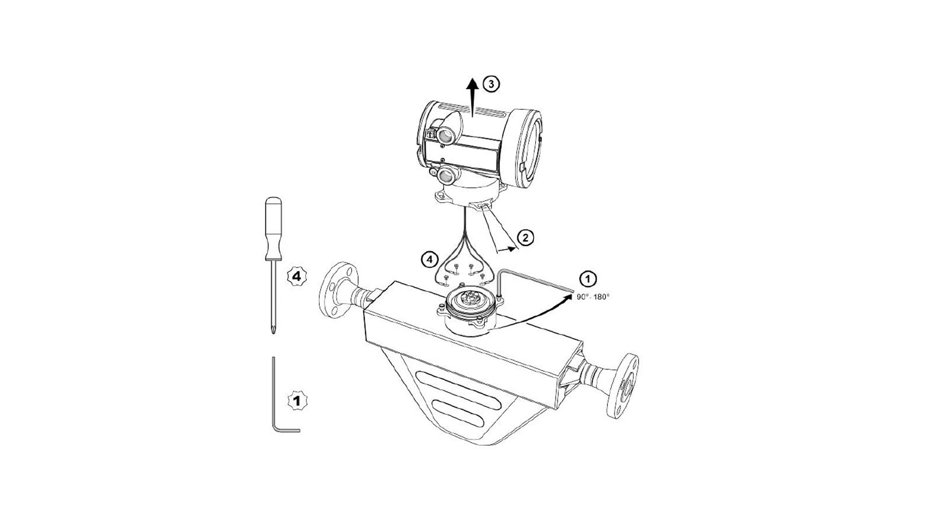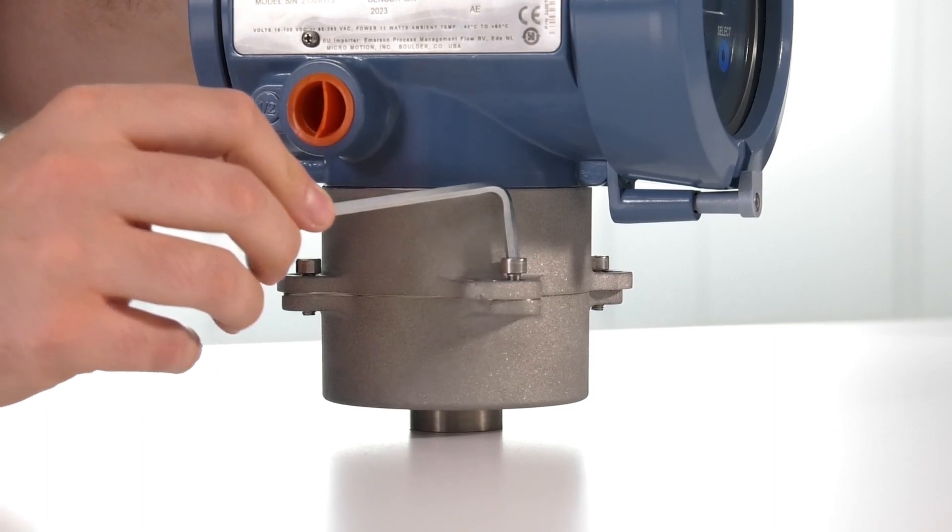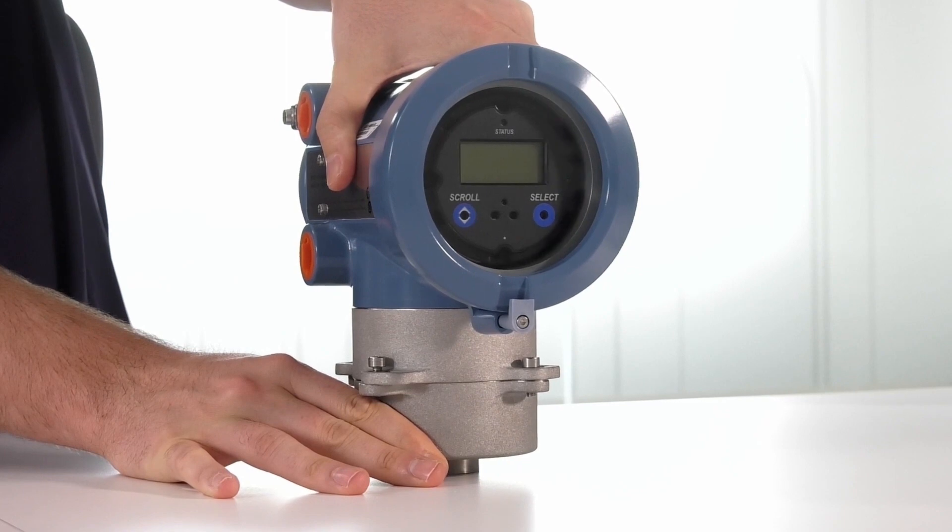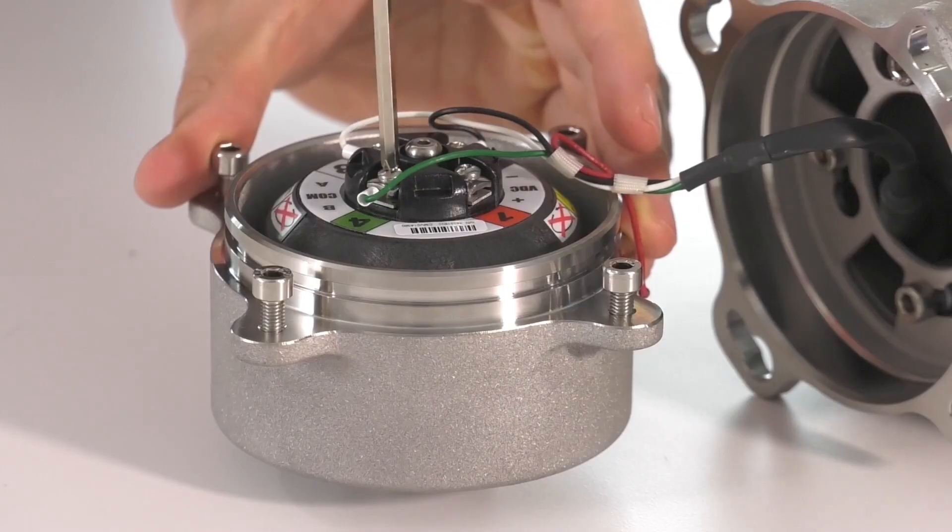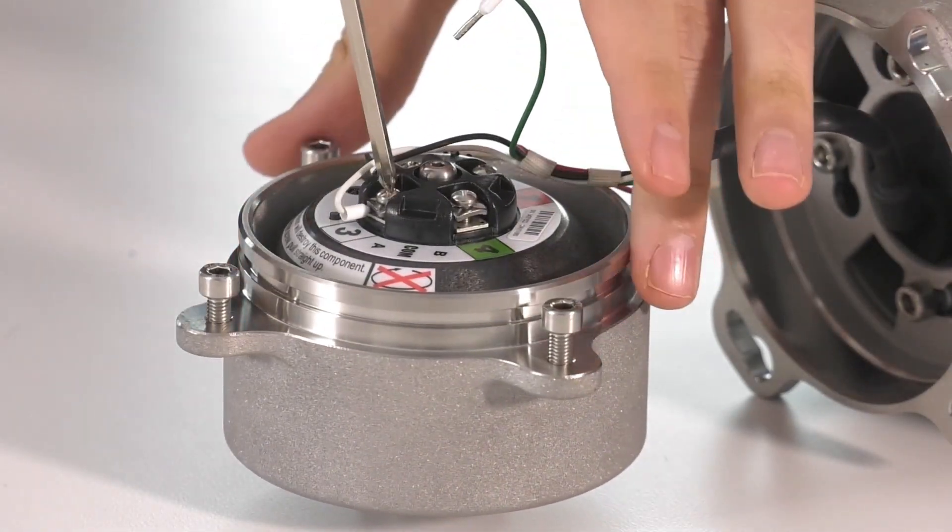First, we will remove the 1700 or 2700 transmitter. Using a four millimeter Allen wrench, loosen the four screws connecting the transmitter to the sensor. Rotate the transmitter mounting bracket anti-clockwise and lift upwards. Disconnect the wires connecting the transmitter to the core processor by using a screwdriver.